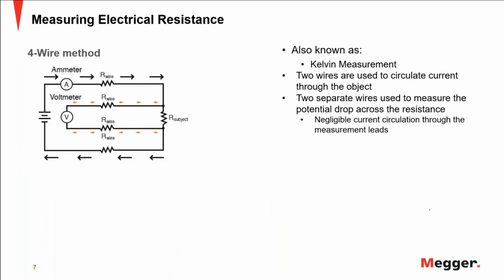Then the four-wire method. In this case, this is also known as the Kelvin measurement. Two wires are used to circulate the current through the object that we want to measure, which is this one. And then two separate cables are used to connect the voltmeter to the object under measurement, or the surface that we want to test. So now the current is going to circulate. You can see the current circulating here.